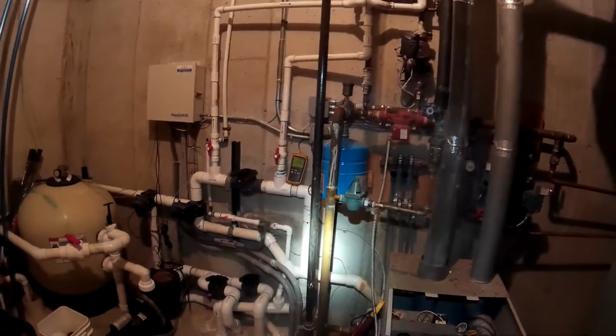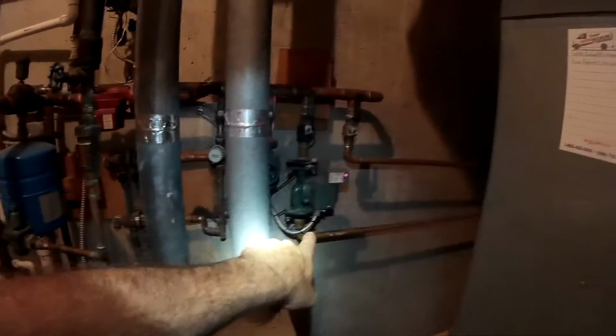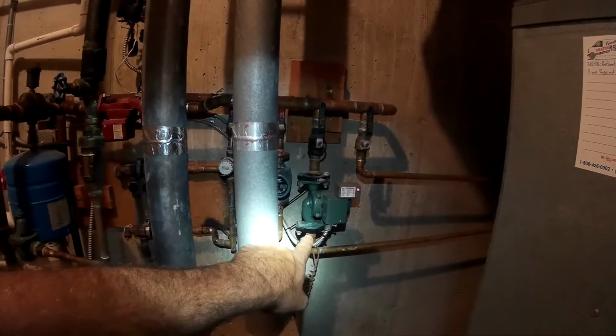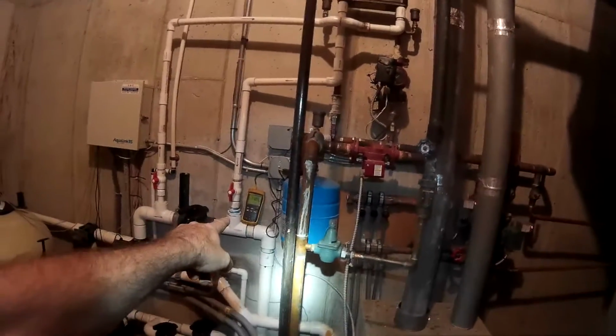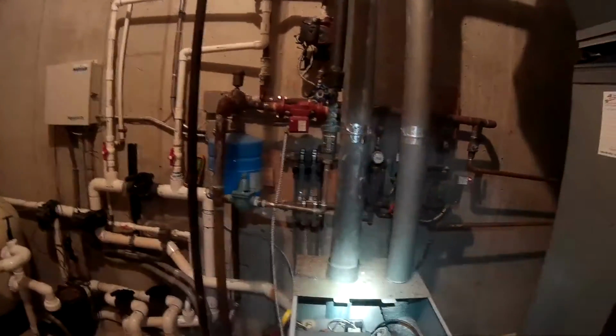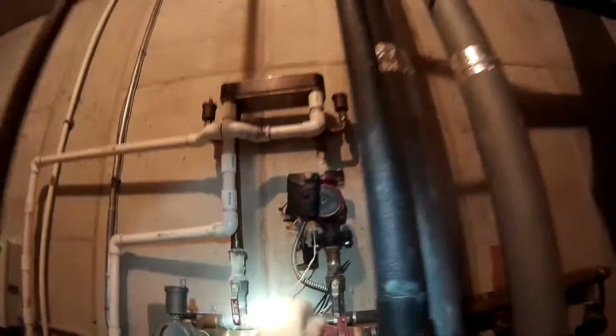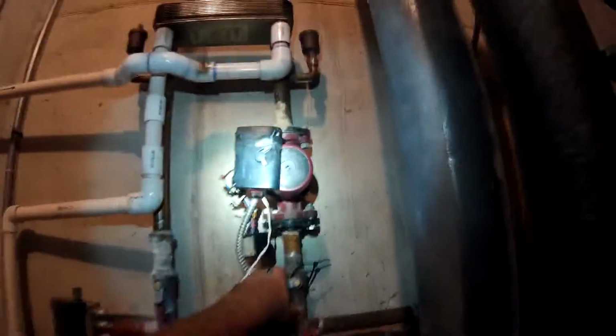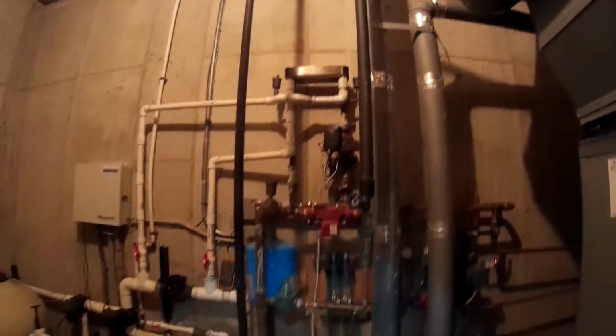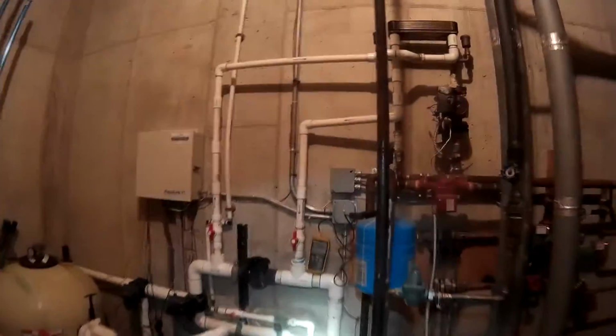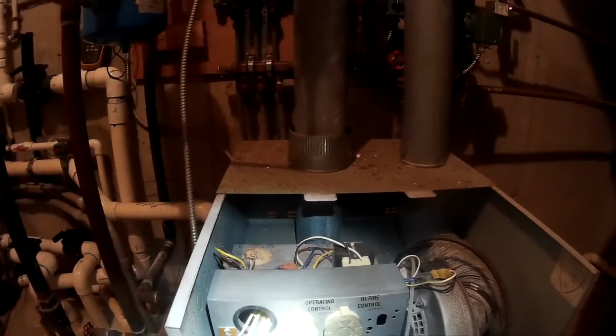And at 124 degrees, I just turned back on. So we'll see how far we go up. Our temperature's dropping because my makeup heat, or my heat for my pool room, just came on, so that's why that dropped so quick. So now what I'll do is I'll close this valve off for right now, just so I can watch the boiler heat up, and I'll close off my pool heat. That's a braze plate heat exchanger for the pool heat. And what I want to do is watch my temperature. Like I said, I'm set at 140 degrees on my operating control.